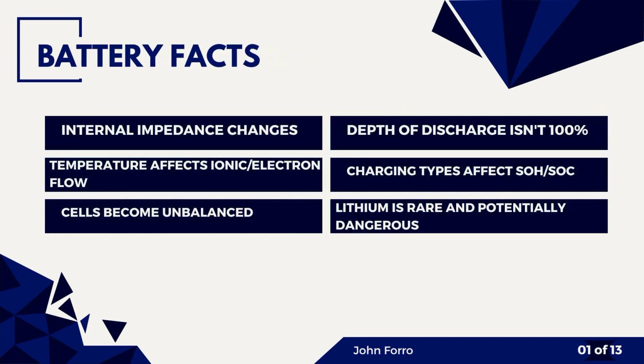Battery facts. We talked about the internal impedance, and we talked about how temperature affects the overall performance of the battery. But why does it? It does it for two reasons. Number one, as we said before, if it's too cold or too hot, the separators could cause a problem with an internal short. But temperature also affects the ionic movement between the anode and cathode, back and forth. The materials that the anode and cathode are made of is battery technology.